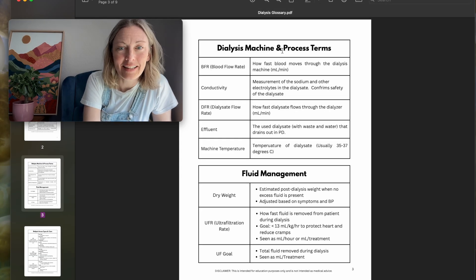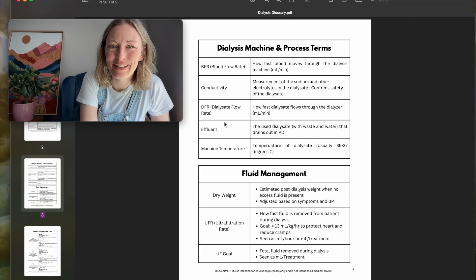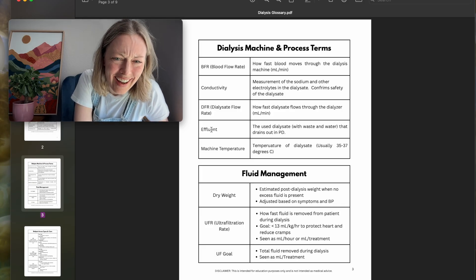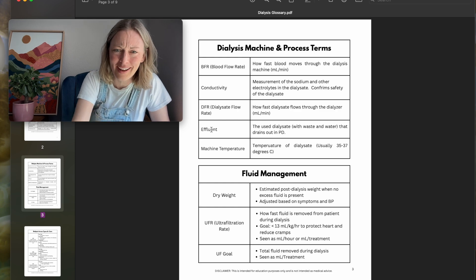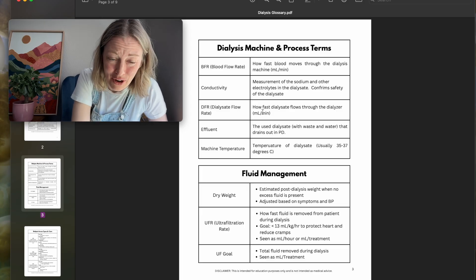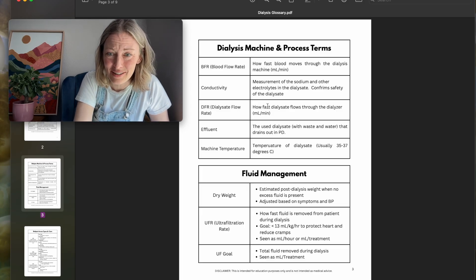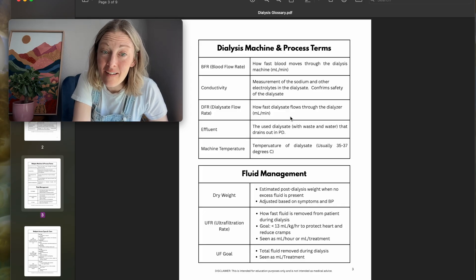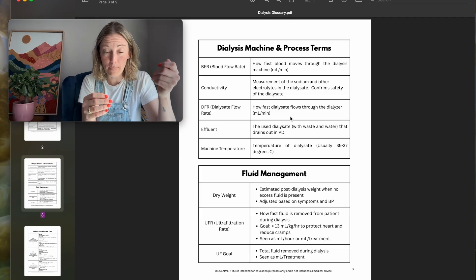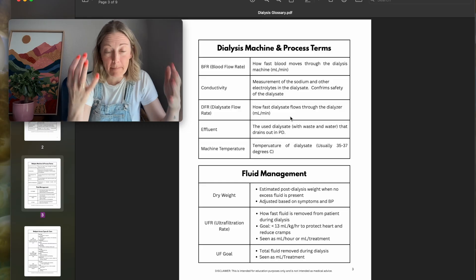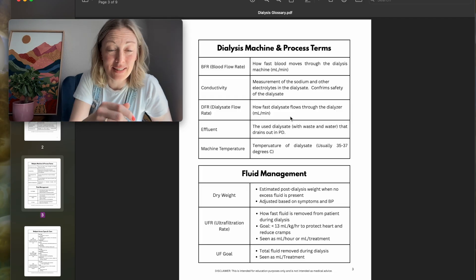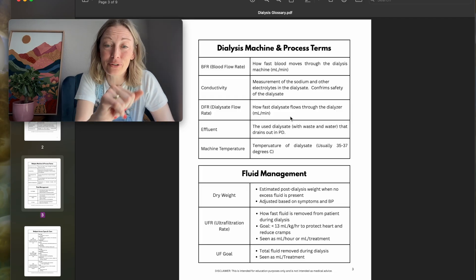My favorite term looking back when I first started was DFR. Dialysate flow rate — 600 mils per minute across that semi-permeable membrane, that dialyzer. That is fast and super cool. Dialysate is part acid, part bicarbonate, and many parts water, so that's why water safety is so important — a lot of water passes across that semi-permeable membrane and we need to make sure the water is safe for the patient.